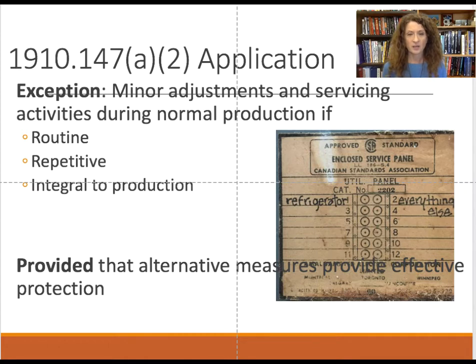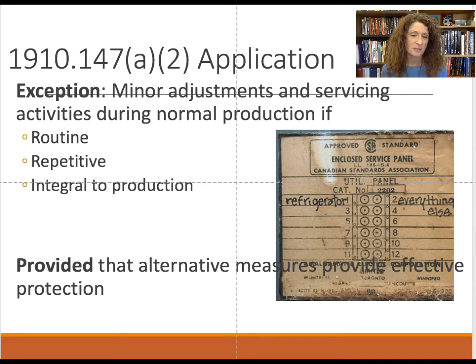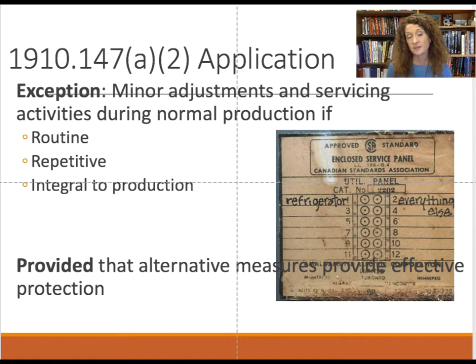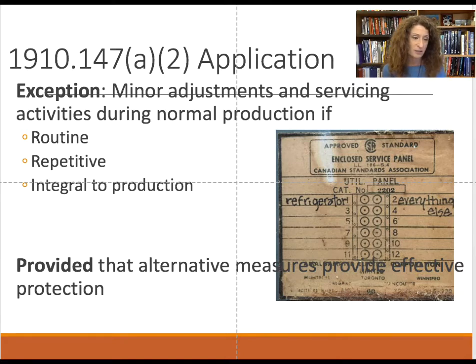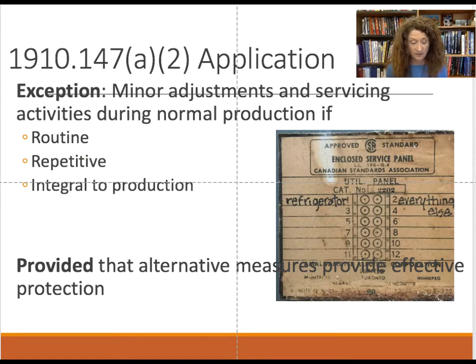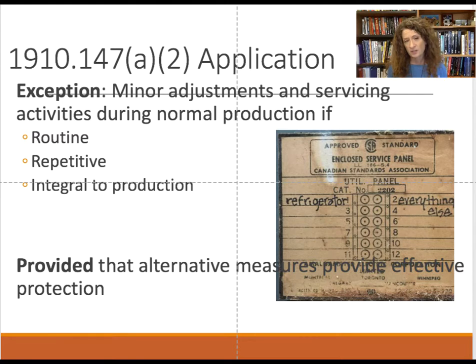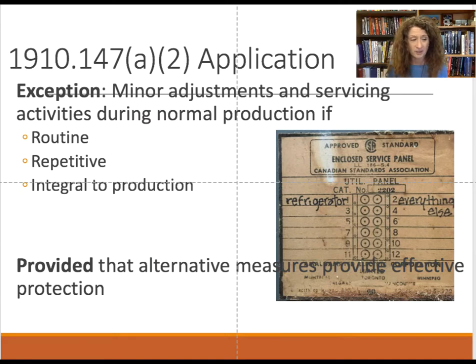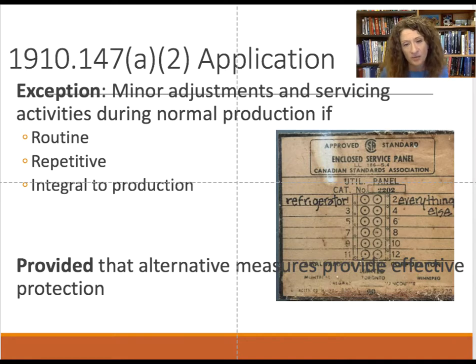Other exemptions to performing lockout-tagout include tasks that are repetitive to the job — for example, constantly lubricating a piece of equipment doesn't require a full lockout. That might be integral to production, such as putting ink on a press, which is part of normal operation and covered under machine guarding. Think of machine guarding as when the machine is operating, versus lockout-tagout when it's shut down for repair or maintenance.